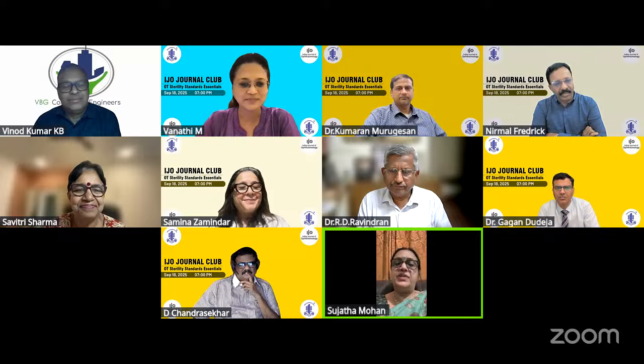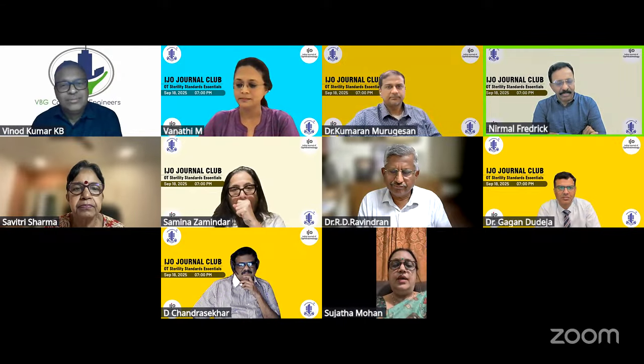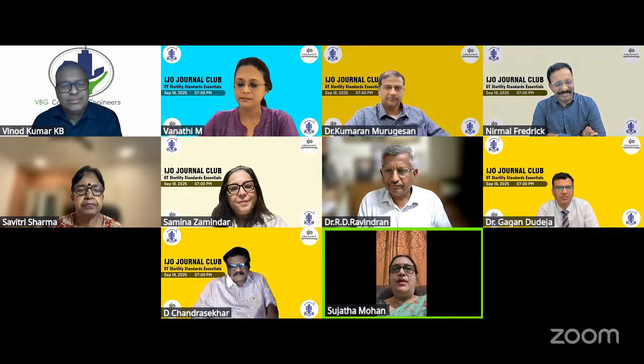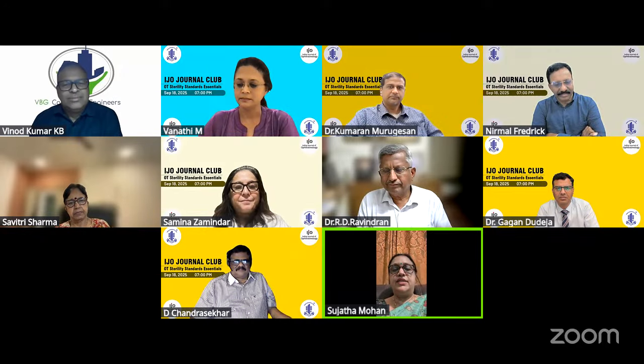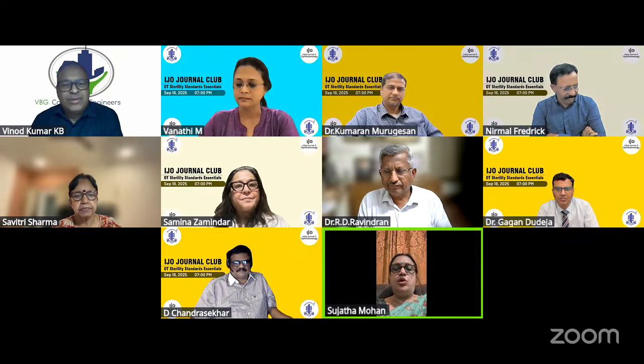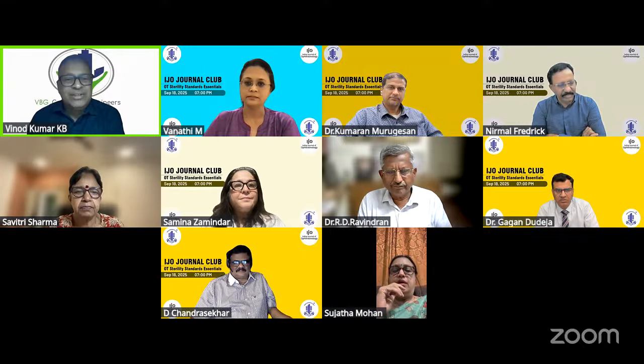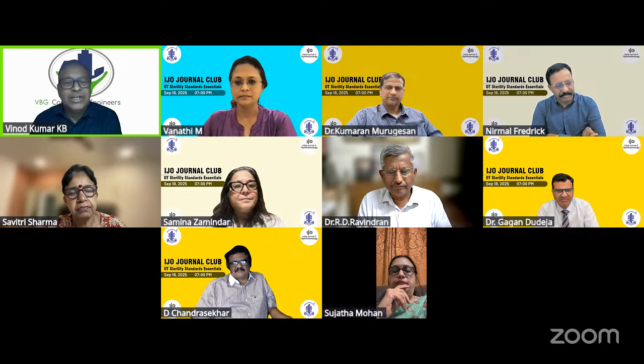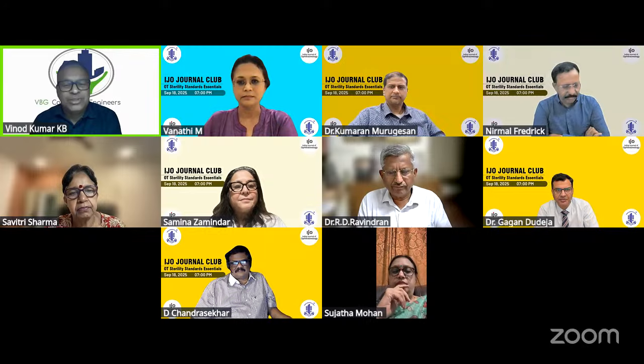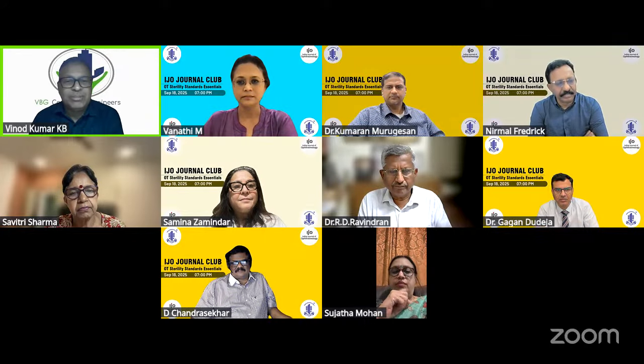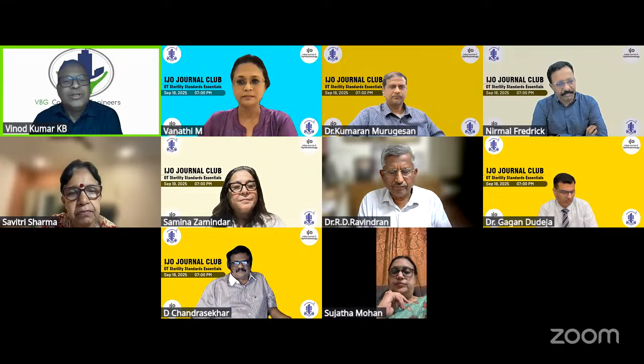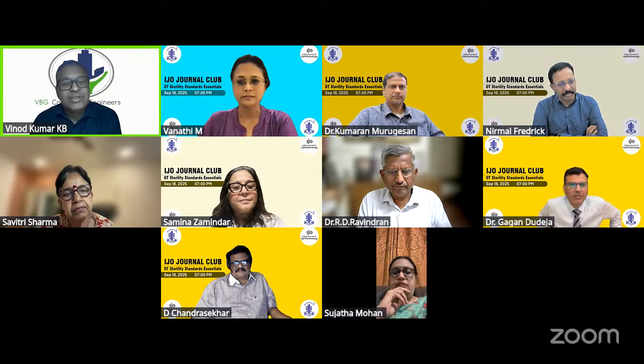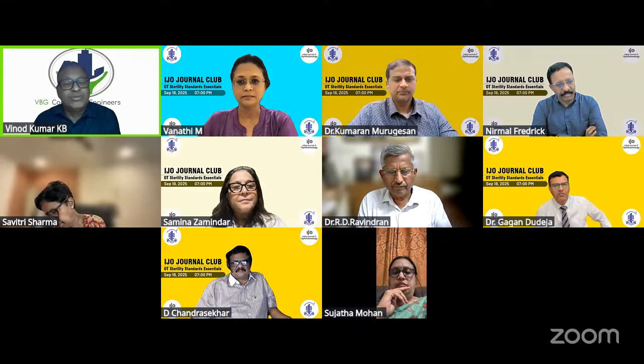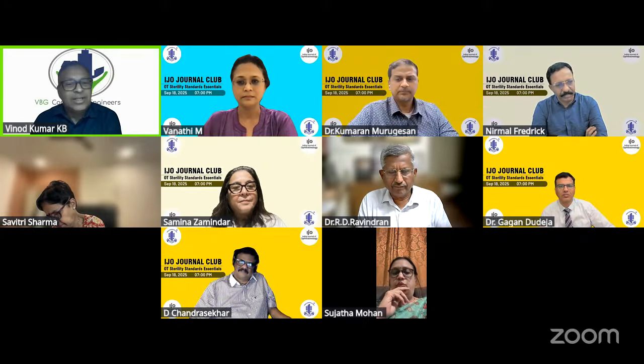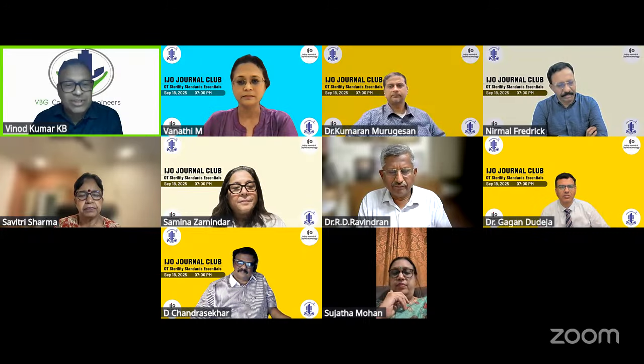Sir, can I ask one question? Yes, madam. I just want to know how often we have to clean the pre-filters and the duct. What is the normal specification? Duct cleaning is not mandatory, doctor, because once you finish the pre-cleaning and the commissioning process, normally you don't need to do that because you're in a very sterile atmosphere. Unless you find that a growth is there, you need to clean the ductwork. Cleaning the ductwork is generally done for kitchen ductwork where there's a lot of grease coming in because of the cooking. That's where the frequency is very, very high.